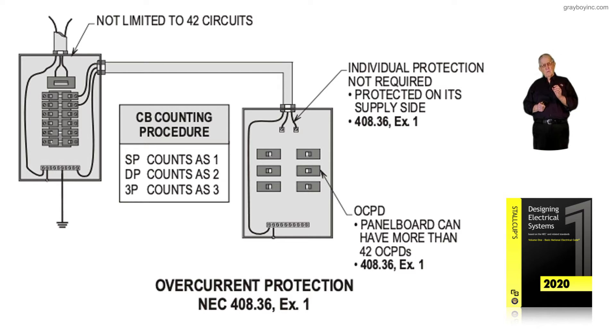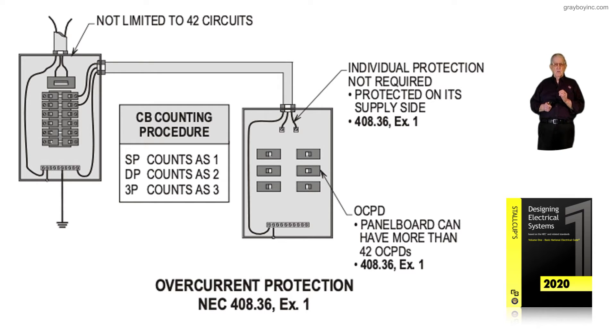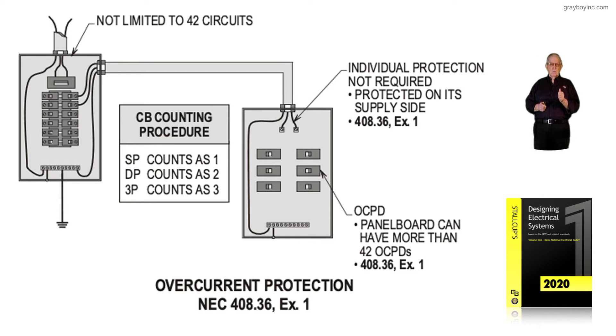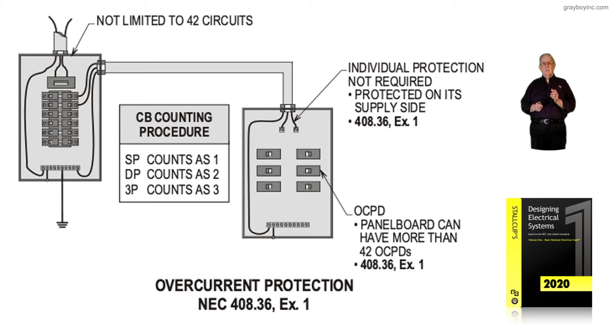We had to determine a way to count these breakers. The circuit breaker counting procedure is listed in the boxed-in information between the two pieces of equipment that you see in the drawing. A single pole breaker counts one, a double pole breaker counts two, and a three pole breaker counts three toward counting the number of circuit breakers in a panel board.